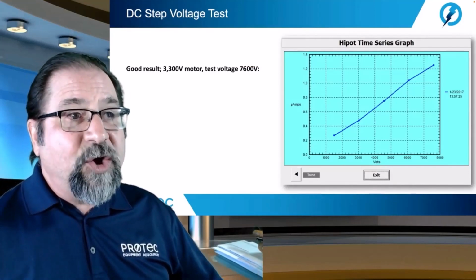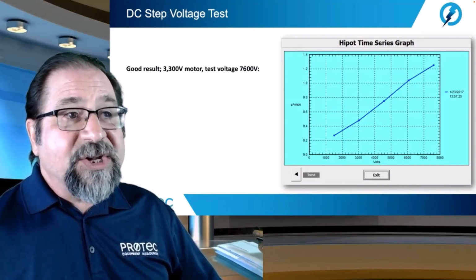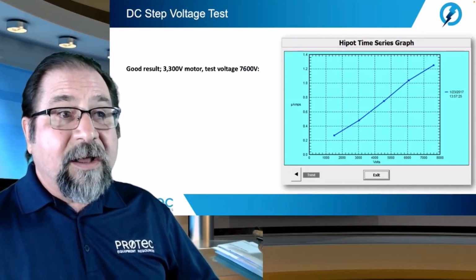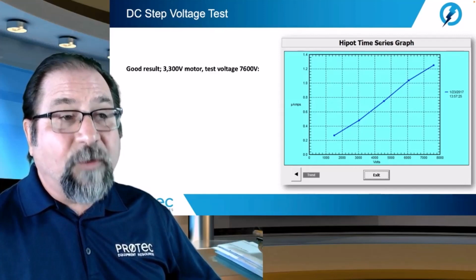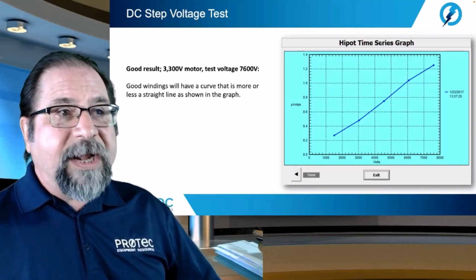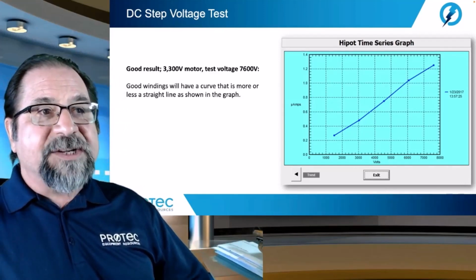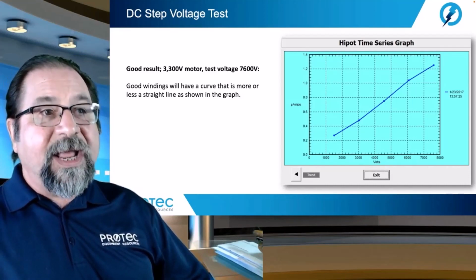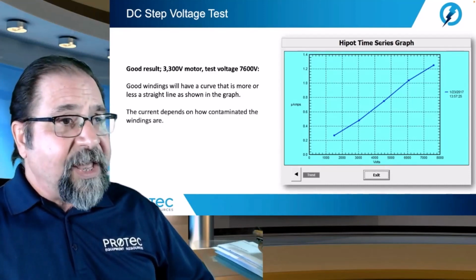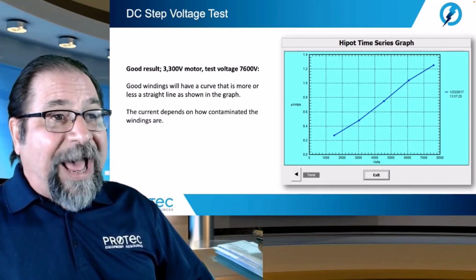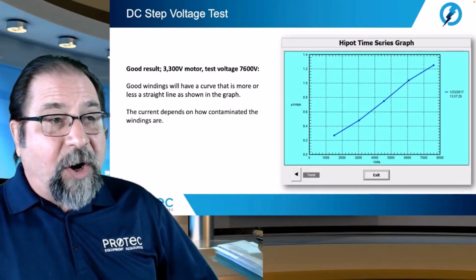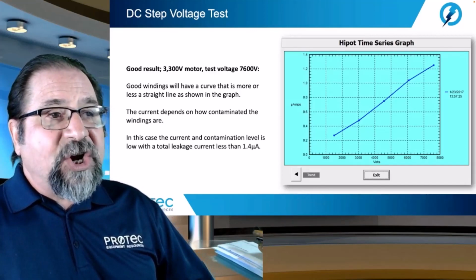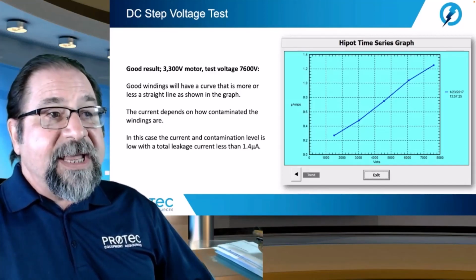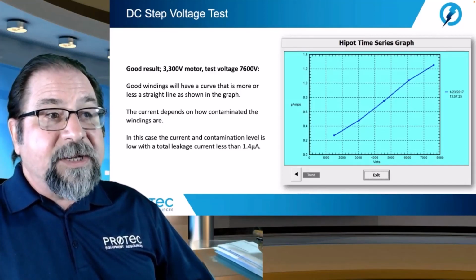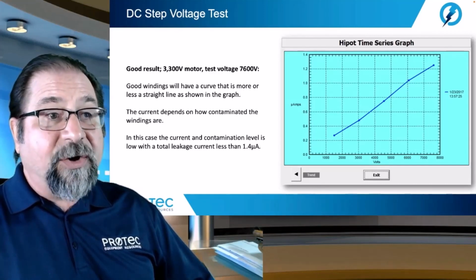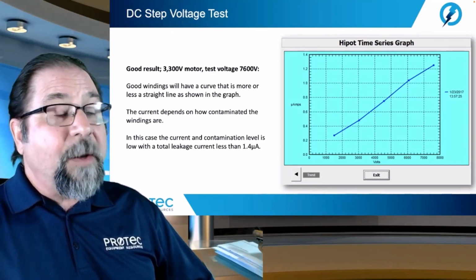Here we have a good result. A 3,300 volt motor was tested with 7,600 volts. Good windings will have a curve that is more or less a straight line, as shown in this graph. The current depends on how contaminated the windings are. In this case, the current and contamination level is low, with a total leakage current less than 1.4 microamps.